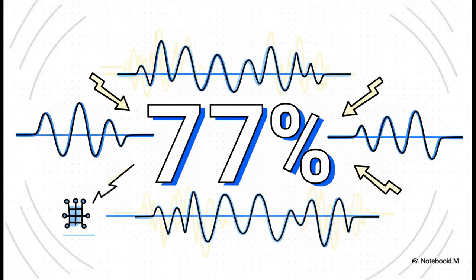And how high can that number get? You're not going to believe this. In a real-world test of a variable speed drive running at a pretty light load, the current distortion, its THD, hit an incredible 77%. Now, the actual amount of current was low, but it just goes to show how wild the distortion can get. And that brings up a really crucial point.